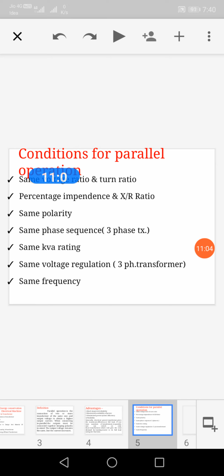Same polarity. What is the polarity? When same input power is being fed to the transformers and the instantaneous direction of individual EMF in the secondary of the two transformers are opposite to each other, the transformers are in opposite polarity. If polarity of parallel connected transformers are not same, what will happen? Large circulating current flows in the transformer but no load is fed. That is why polarity should be same.